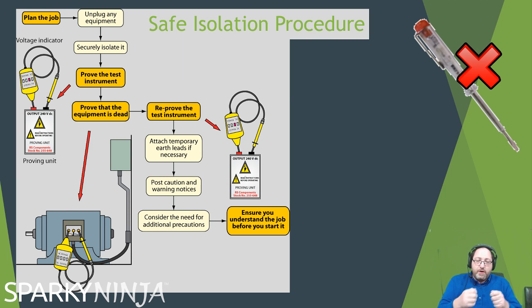And then we're going to go to the point of isolation, and we're going to prove isolation by going on the live conductors and the earth and the neutral. And there is a sequence. Yeah, so you go on the line last to come off the line first.